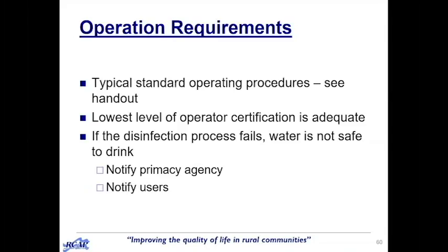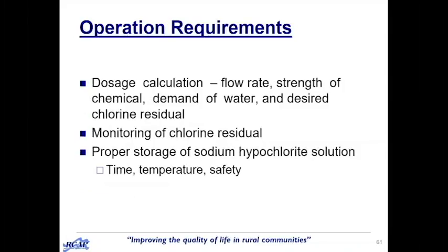So some more operating requirements, things like the fact that you do have to do a dosage calculation. And it's based on flow rate and the strength of your hypochlorite solution, and what sort of chlorine demand you've got and what residual you're wanting to maintain in the system.